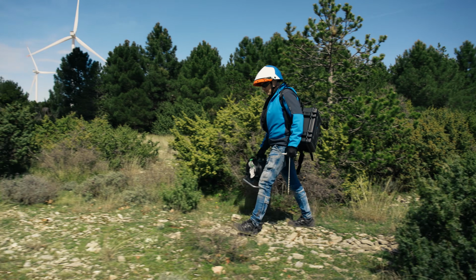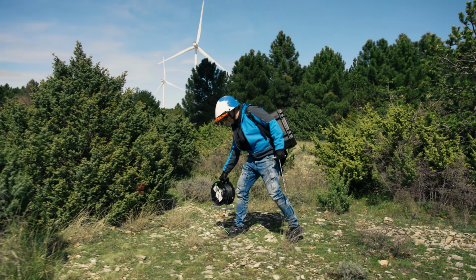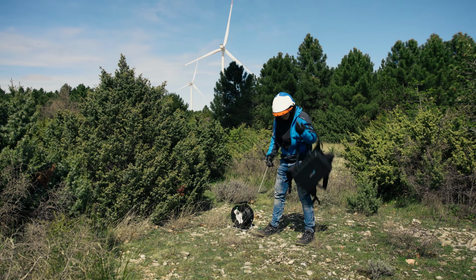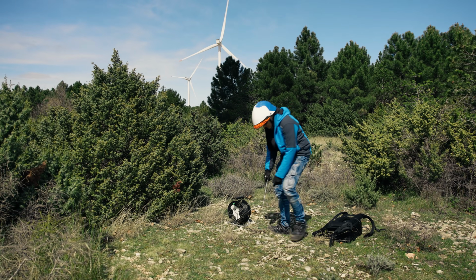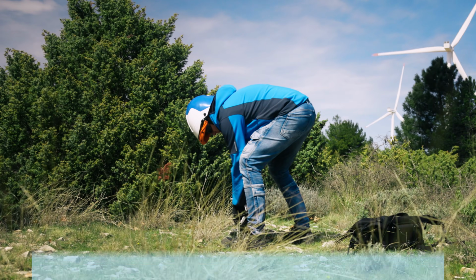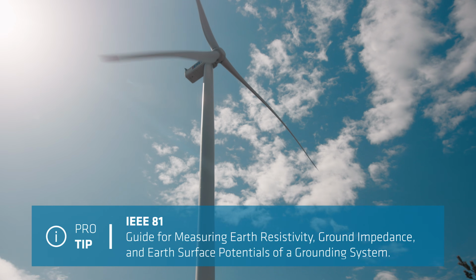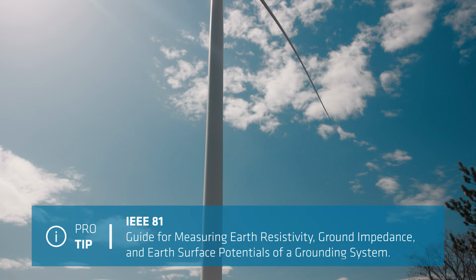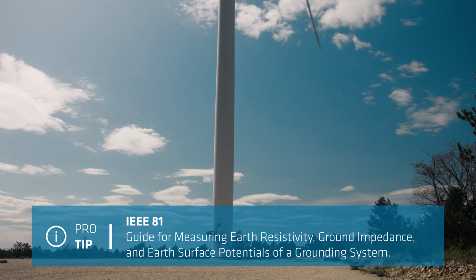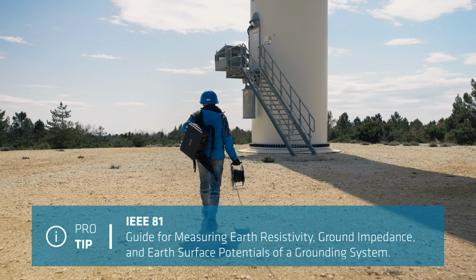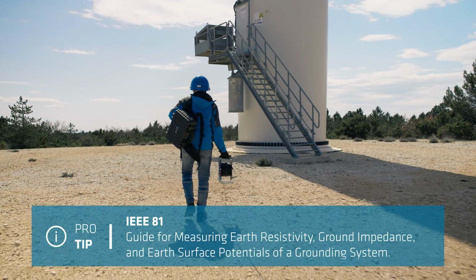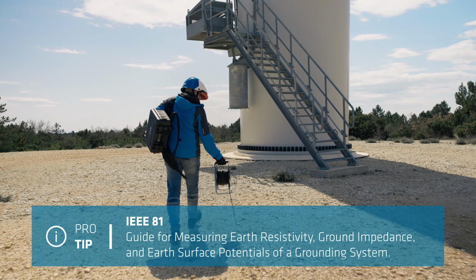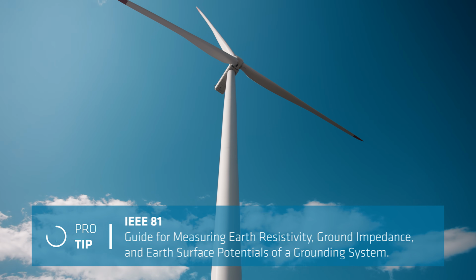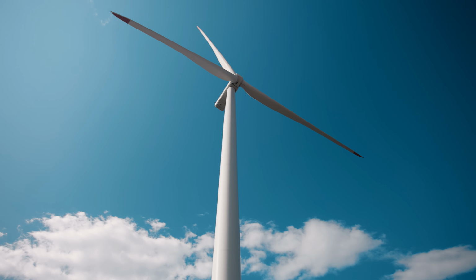On the ground, or more precisely in the ground, this involves measuring touch and step voltages and verifying equipotential bonding. There are several standards that provide guidelines for testing grounding systems, including the measurement of earth resistivity, ground impedance, and voltage distribution during transient events. These standards help ensure that the grounding system performs reliably under normal, fault, and lightning strike conditions.